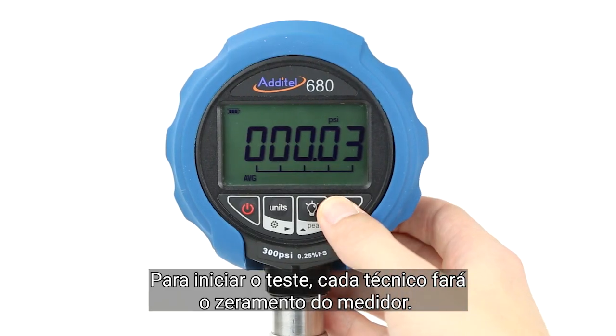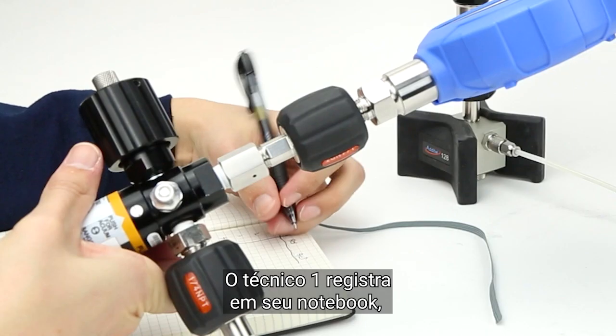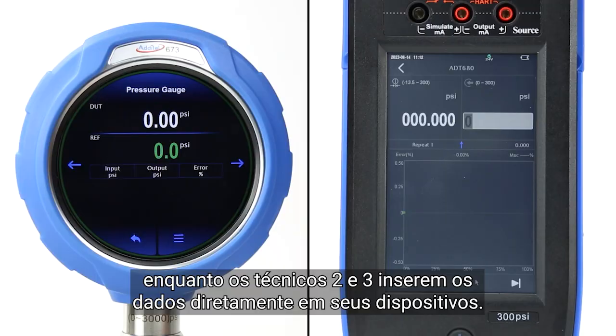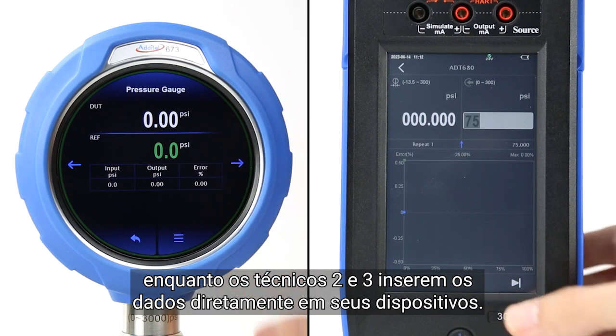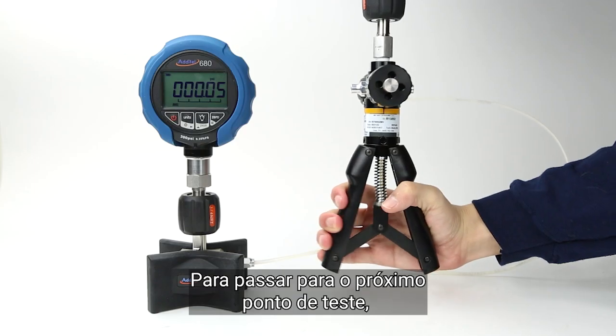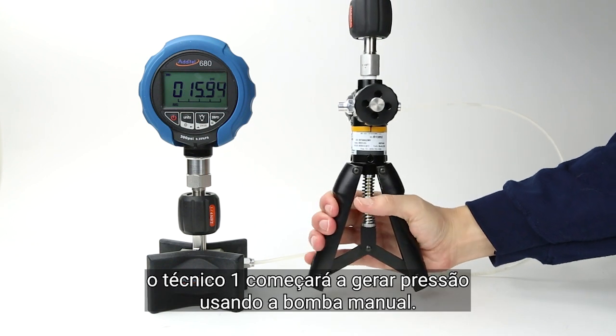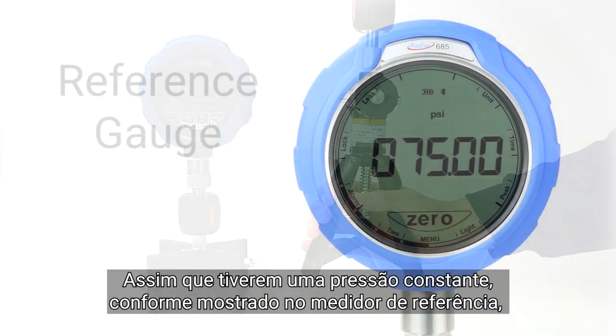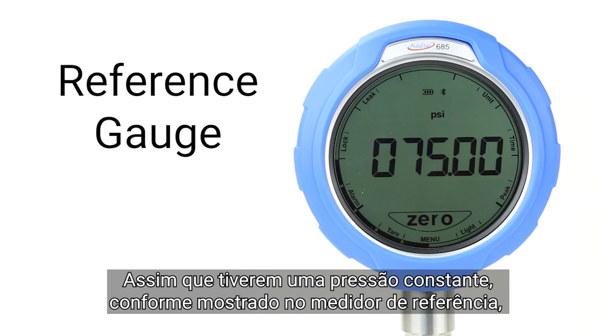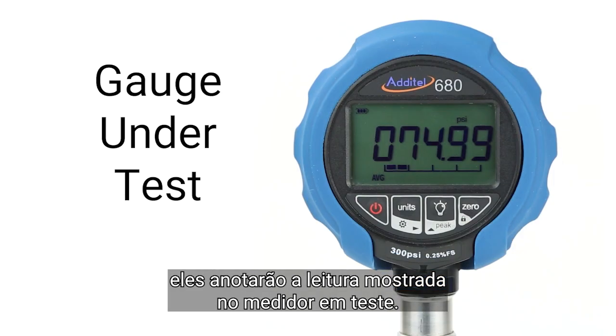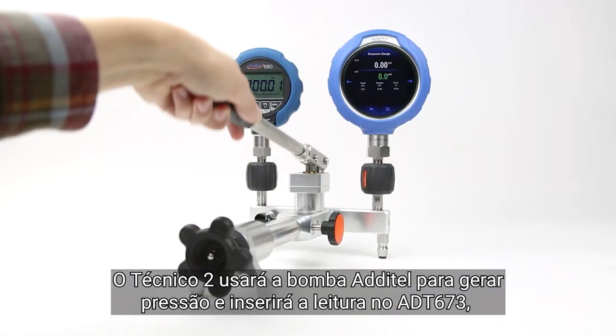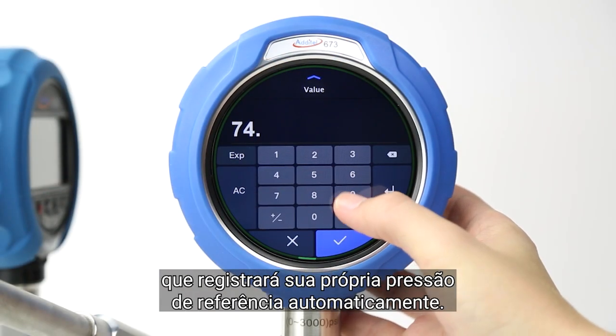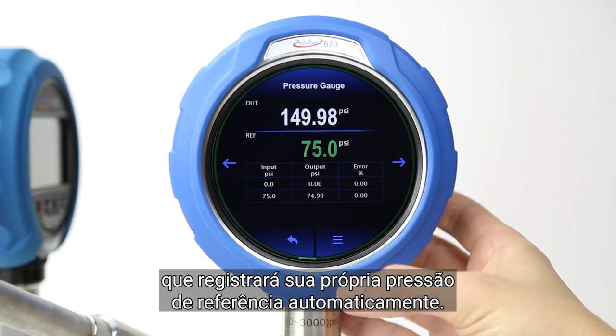To start the test, each technician will zero the gauge. Technician 1 records it in their notebook, while Technicians 2 and 3 enter the data directly into their devices. To move to the next set point, Technician 1 will begin to generate pressure using the hand pump. Once they have a steady pressure as shown on the reference gauge, they will write down the reading shown on the gauge under test. Technician 2 will use an Additel pump to generate pressure and enter the reading into the 673, which will record its own reference pressure automatically.